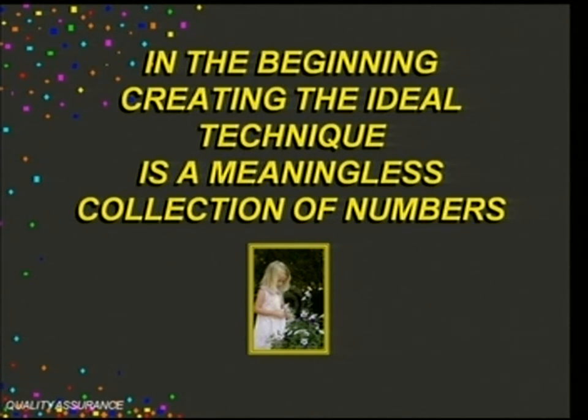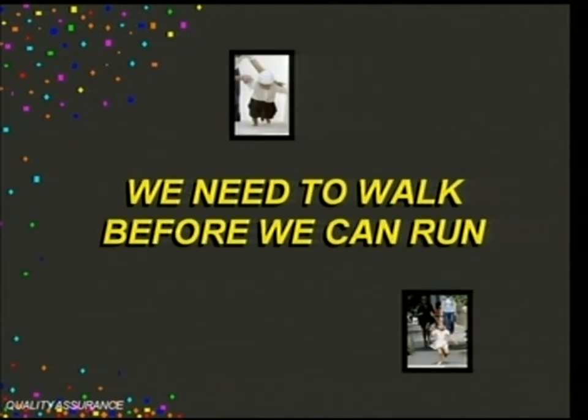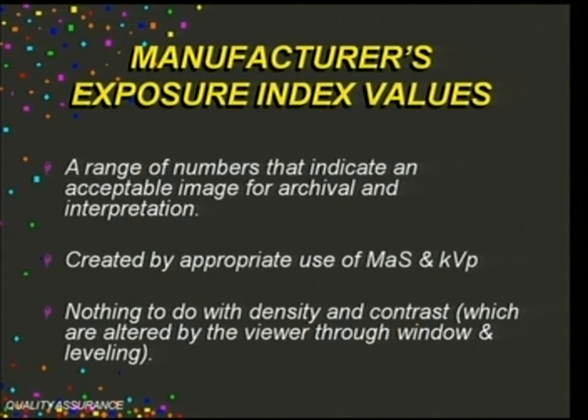Okay, so going back to that lost visual connection between what we set on the control panel and the resulting image, remember that there's a correlation now between your exposure index values and what you're setting on the control panel. This is going to help you to form techniques to lower patient dose. All right, so now we're going to talk about creating a technique chart that can be of value to us no matter what exposure, no matter what size your patient is.